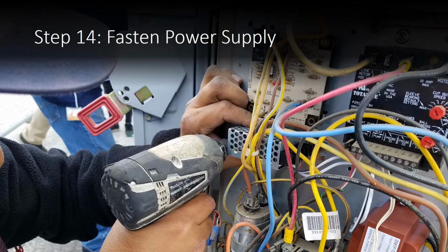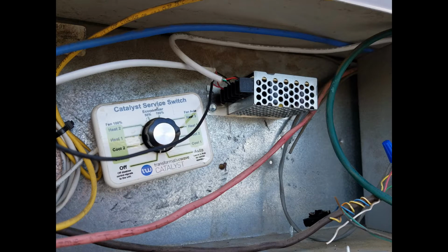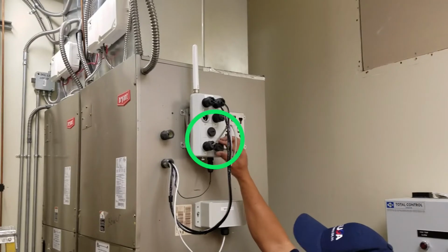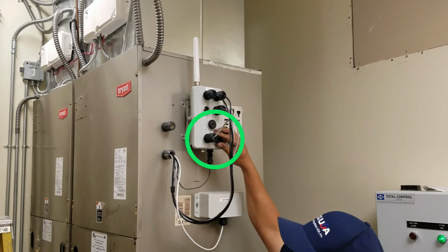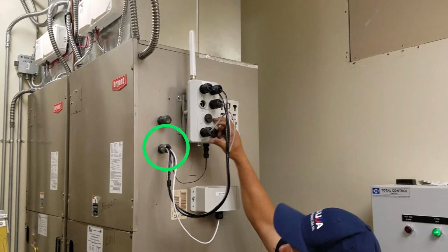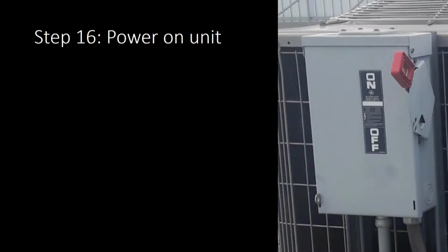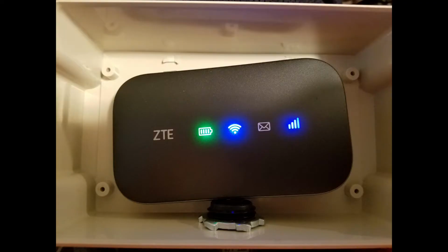Step 14. Fasten the power supply to the interior of the unit using sheet metal screws. Lastly, plug power supply cables into the modem and DCU. Step 15. Close the DCU. Use port plugs to close up unused ports on the DCU, and seal the hole from Step 5 with silicone if it is not airtight. Step 16. Power. Turn on power to the HVAC unit. Check the modem LED to ensure that it is online and close the modem case.